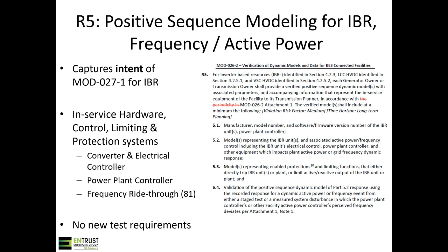and observe how that plant controller would behave. Of course, due to the nature of inverter-based resources, a lot of times you would need to curtail the plant to really see that well for under frequency, because when they're maxed out, they won't rise any higher. But that's one of the details the industry is used to. That's not dissimilar from what you see on a combustion turbine with thermal limits. So pretty cut and dry what we see for R5.